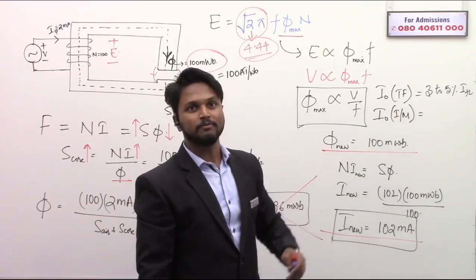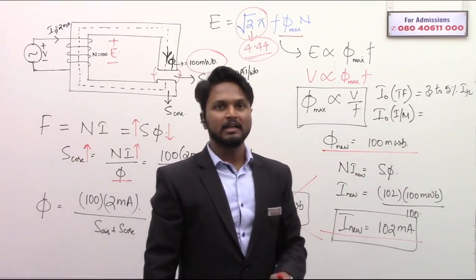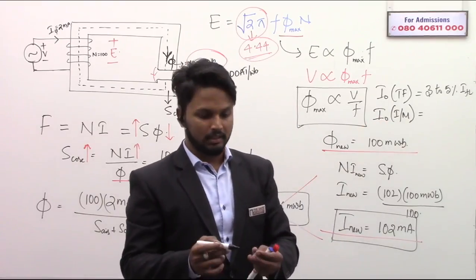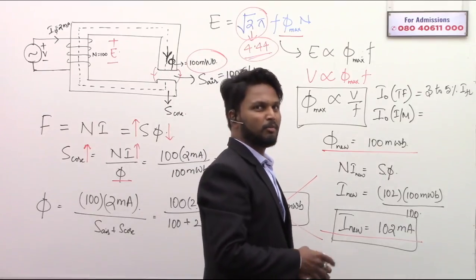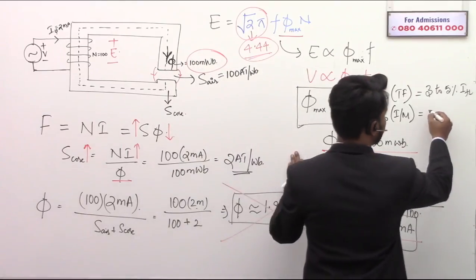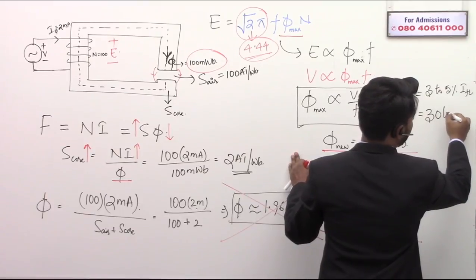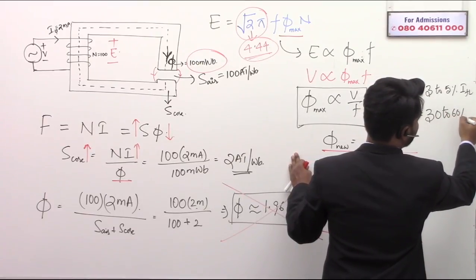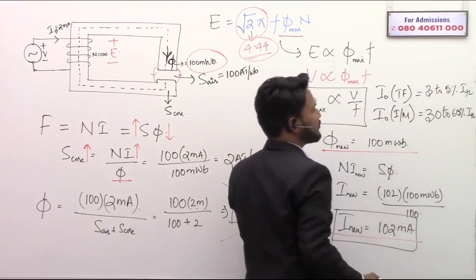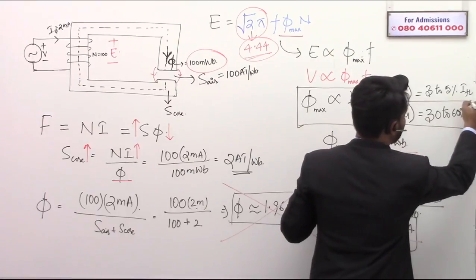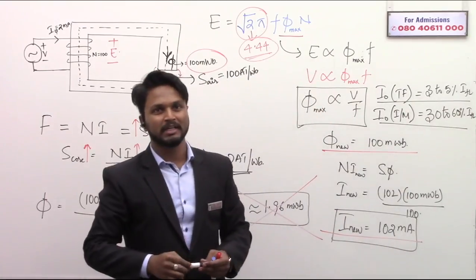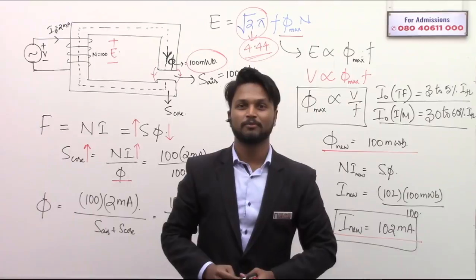Whereas in the case of an induction motor, you are almost right but there's a slight correction needed. In induction motors, it is 30 to 60% of full load current, whereas in a transformer it is 3 to 5% of full load current.